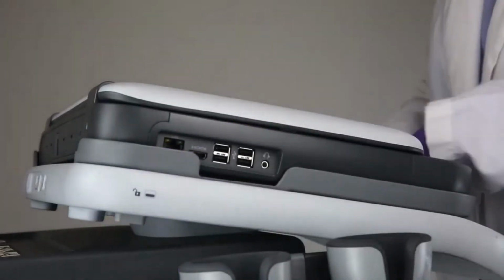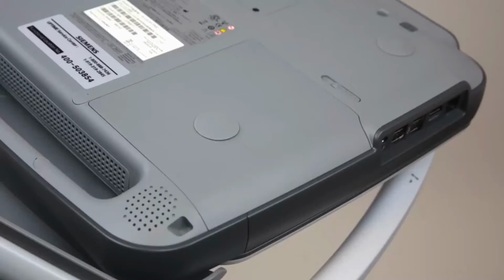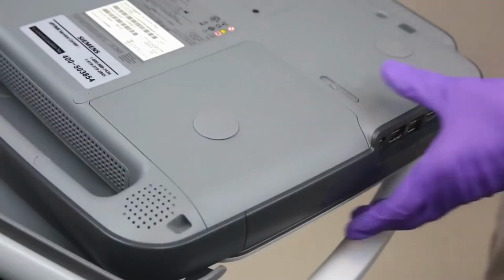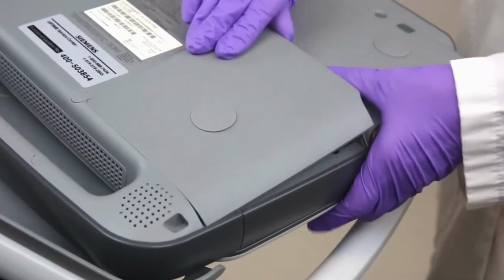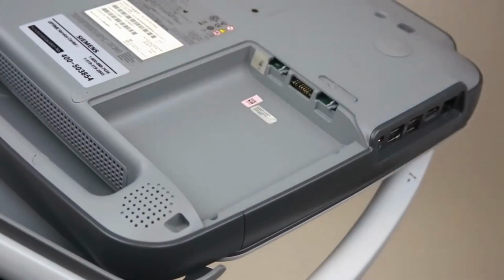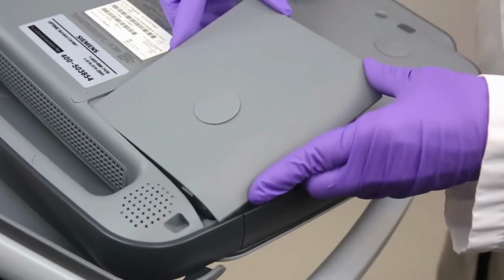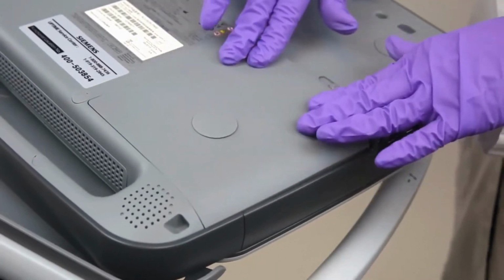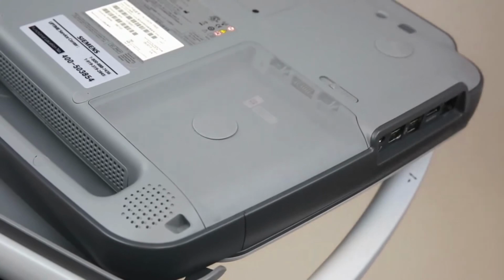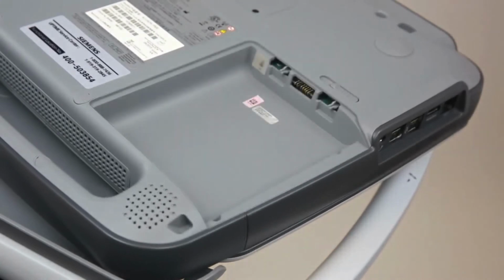To remove the battery, remove the Acuson P500 system from the smart cart. The battery is located under the Acuson P500 system. To remove the battery, slide the release until the battery pops out. Slide the battery into the slot and press until you hear a click to install the battery. It is recommended the battery be removed when the system is being cleaned, stored, or maybe in a situation where it is hot, such as in a car.